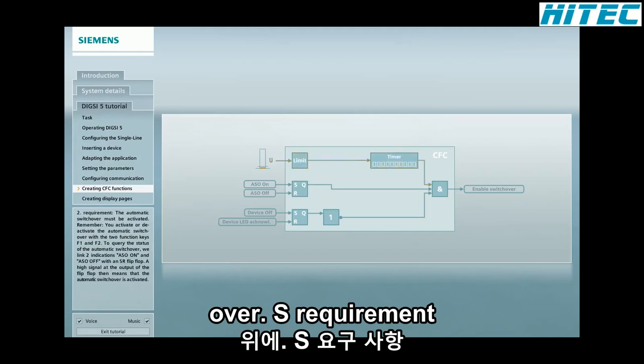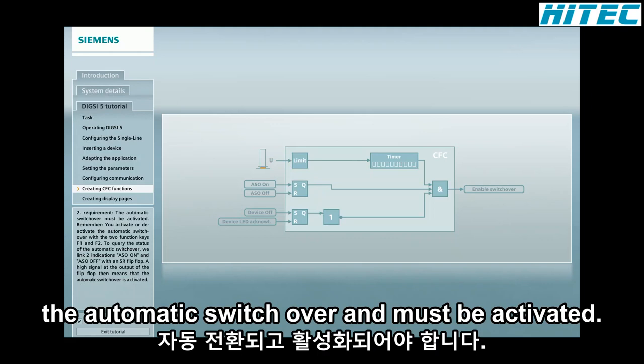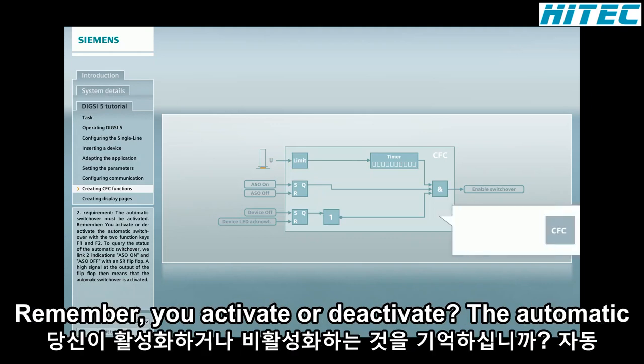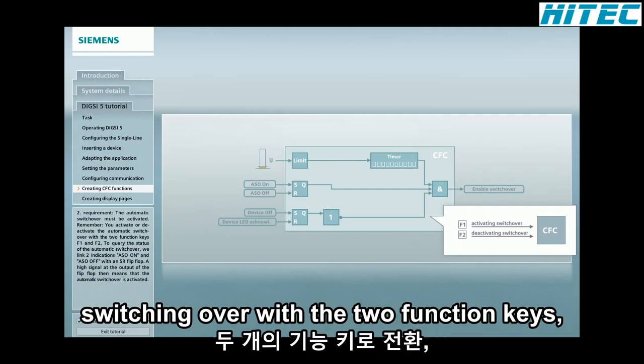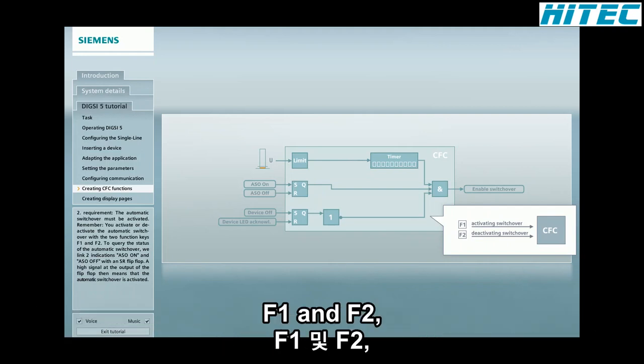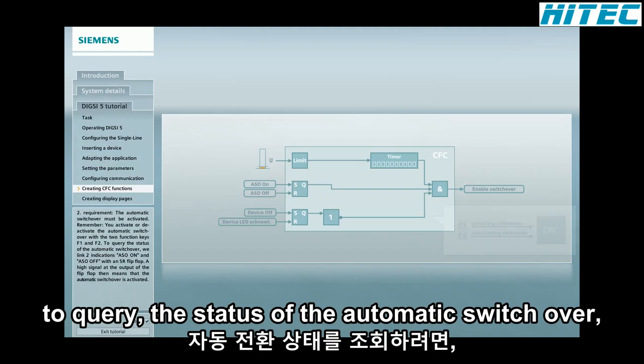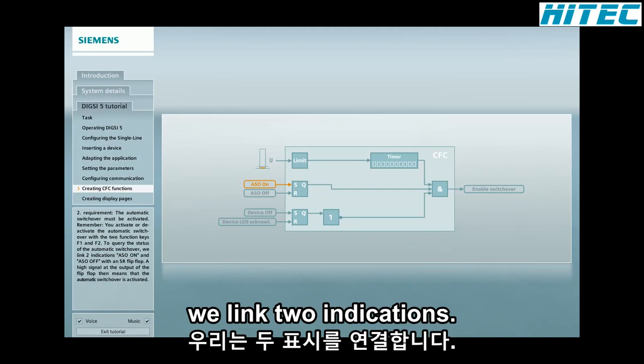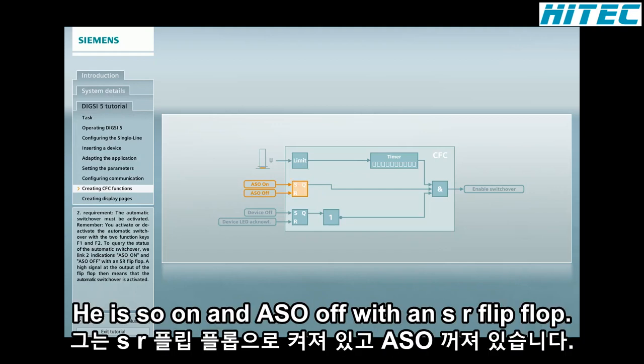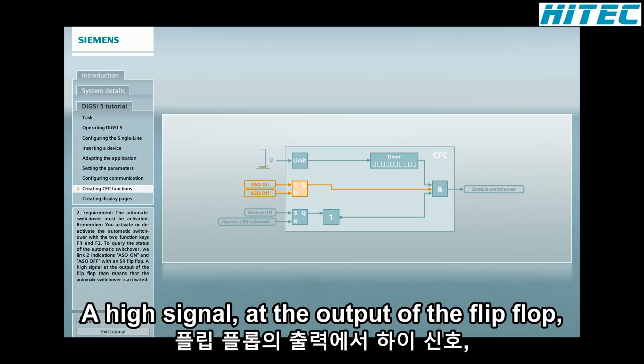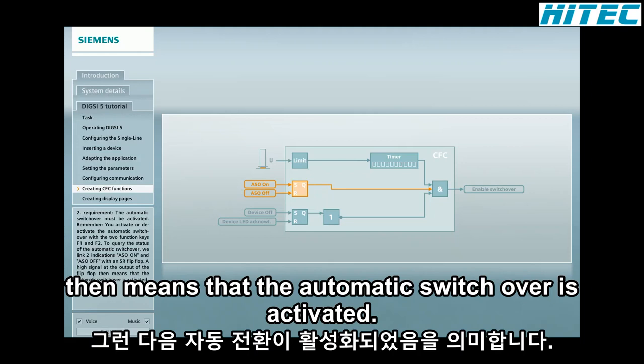Second requirement, the automatic switchover must be activated. Remember, you activate or deactivate the automatic switchover with the 2 function keys F1 and F2. To query the status of the automatic switchover, we link 2 indications, ASO on and ASO off, with an SR flip-flop. A high signal at the output of the flip-flop then means that the automatic switchover is activated.